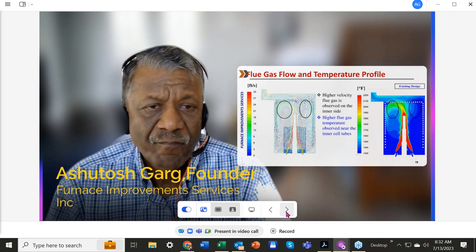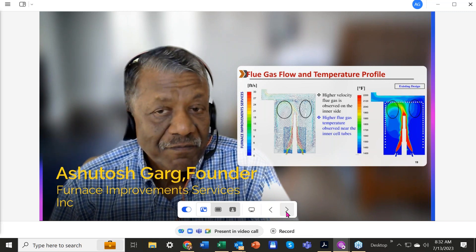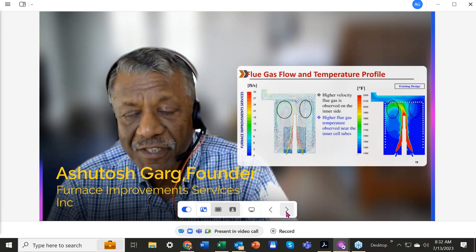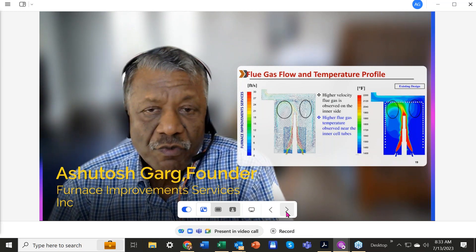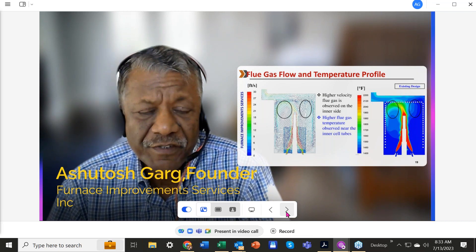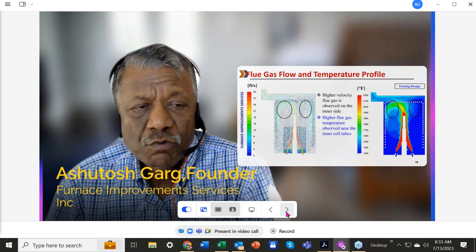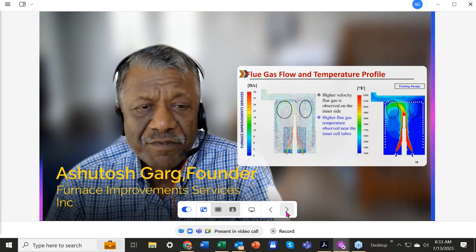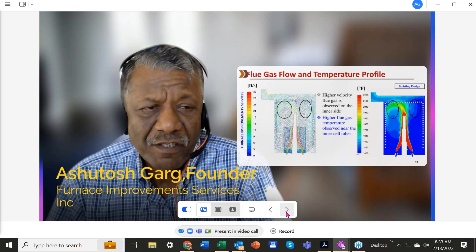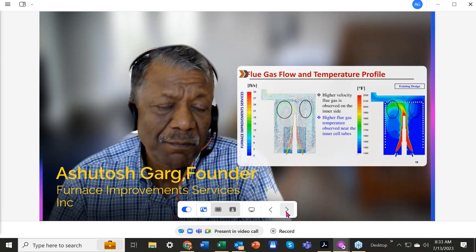We took on this project. I want to tell you about something significant from the last 30 years: the development of CFD — computational fluid dynamics. It is a very powerful tool to analyze fire heaters, used worldwide in many applications including automobile design. We found it to be very useful to analyze fire heaters, look at the flames, and gain insight into what is happening with burners, flue gas temperatures, and tube metal temperatures — including why some particular tubes experience high temperatures and not others.